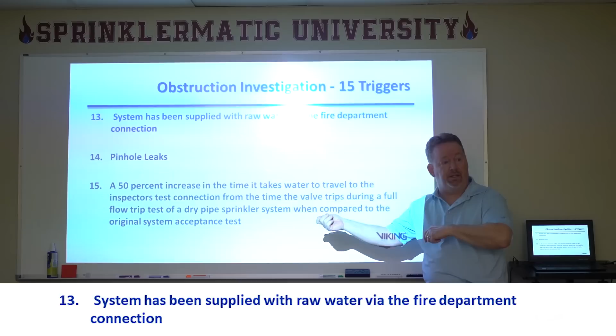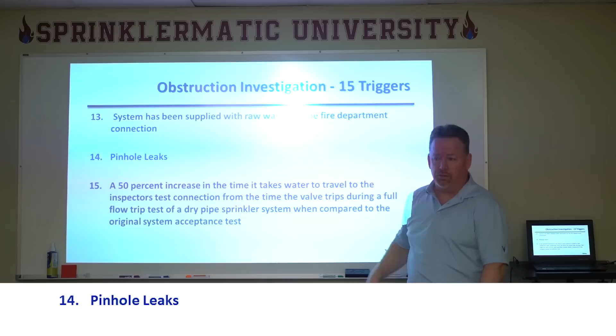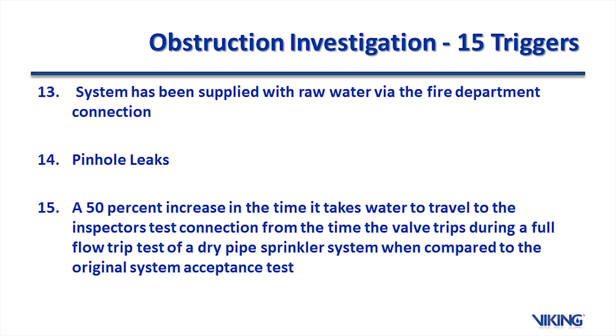Pinhole leaks. Pinhole leaks are one of the characteristics of microbiologically influenced corrosion. It's just one of them; there are a few others. But pinhole leaks are an indication of corrosion to a point where you probably have some material flaking off in the corrosion, and especially if it's MIC, it's going downstream.